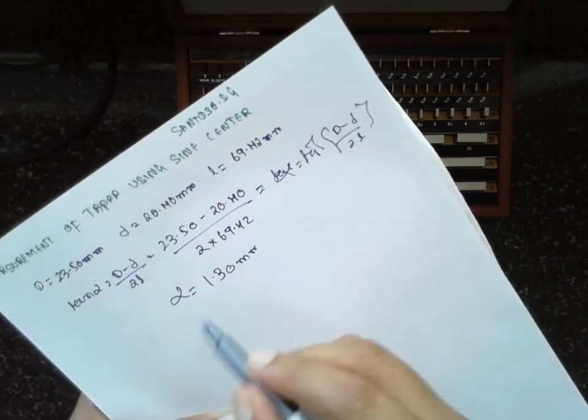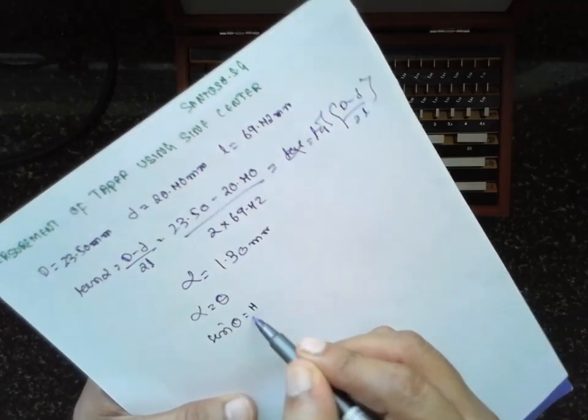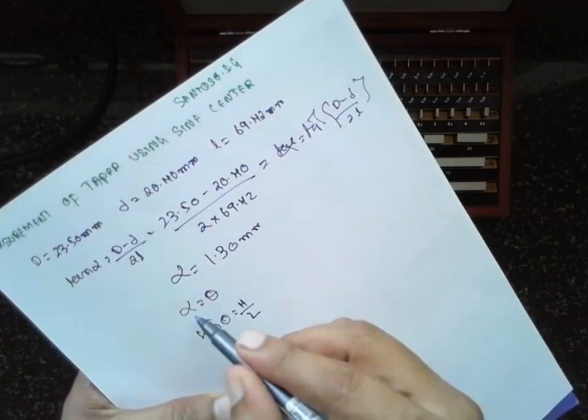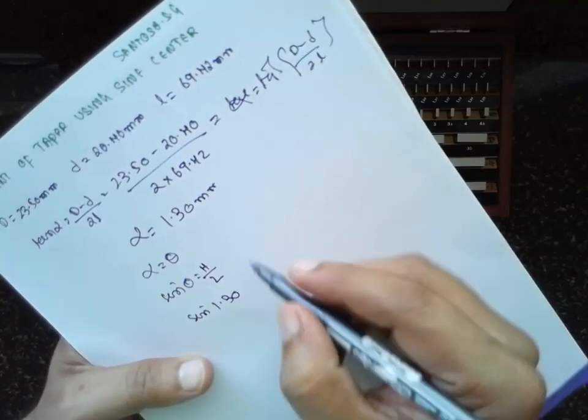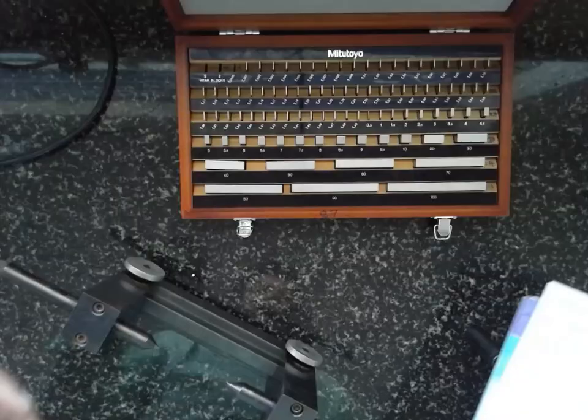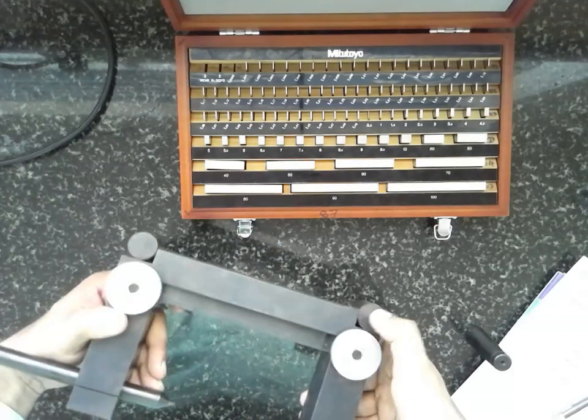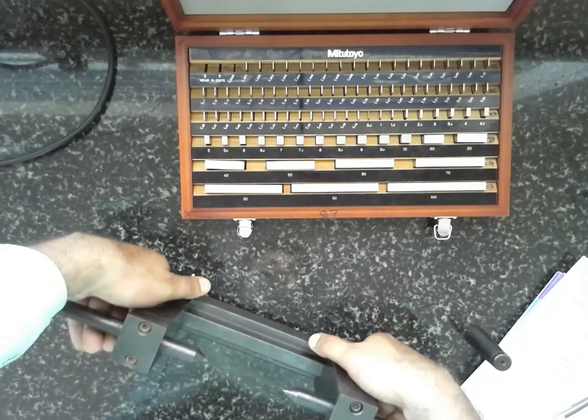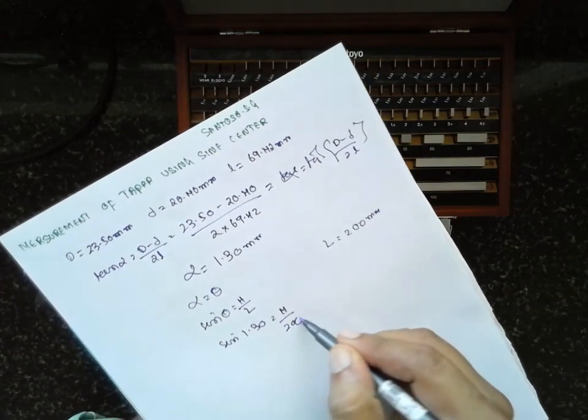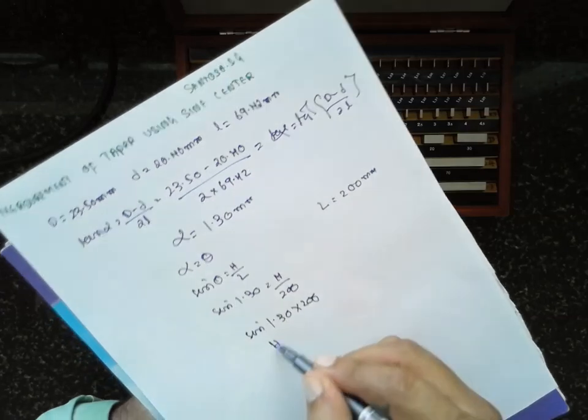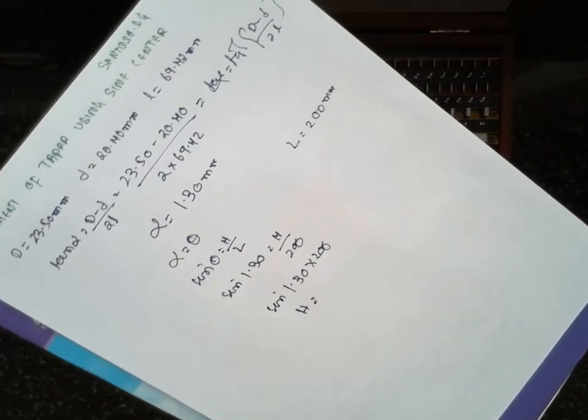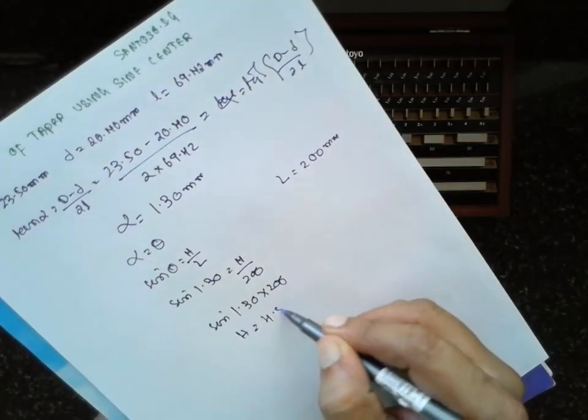As per the trigonometric function, this alpha is equal to theta. What is theta? Sin theta is nothing but h by L. Now, what is theta in the place of alpha? You have to write sin 1.30 equals h divided by 200. How this 200 is obtained? This is the distance between these two rollers. If you cross multiply, sin 1.30 into 200, the h will be around 4.53 mm.